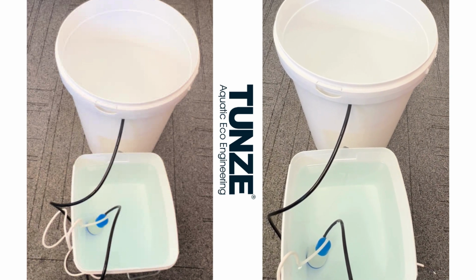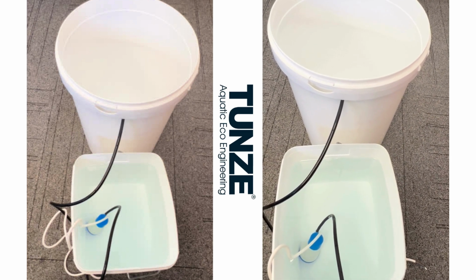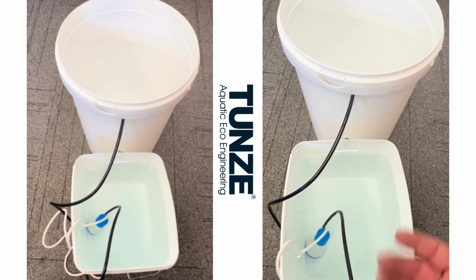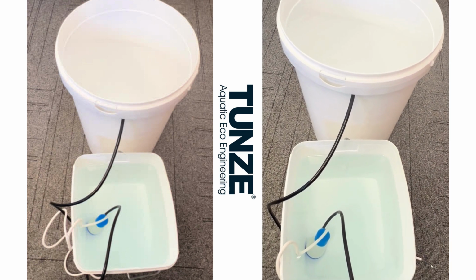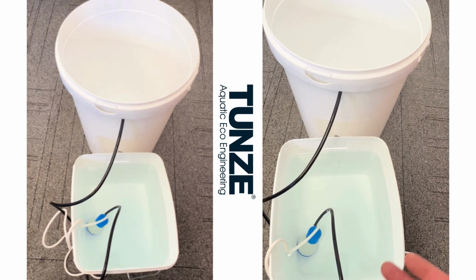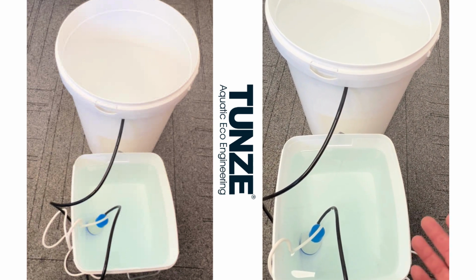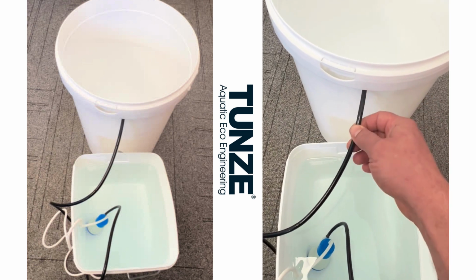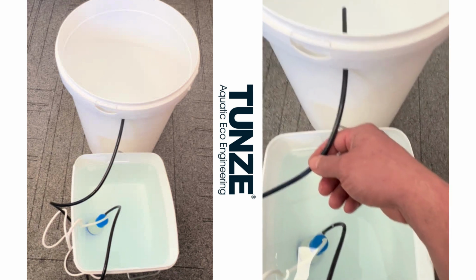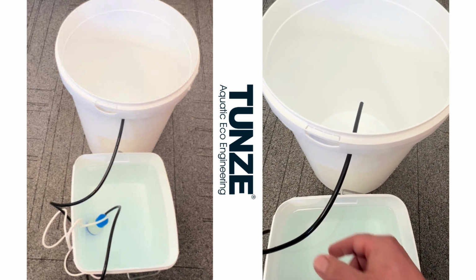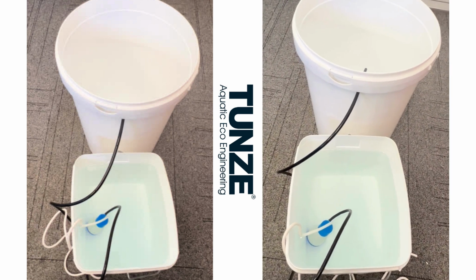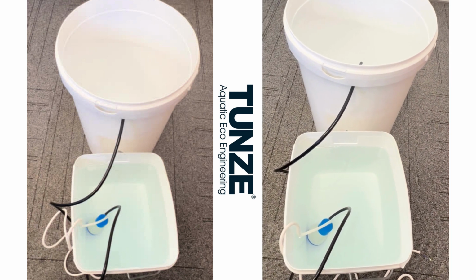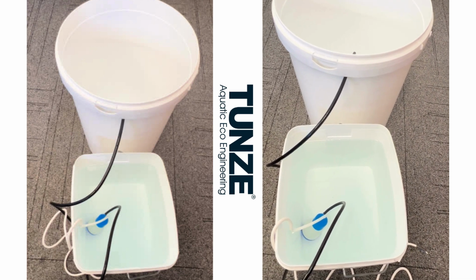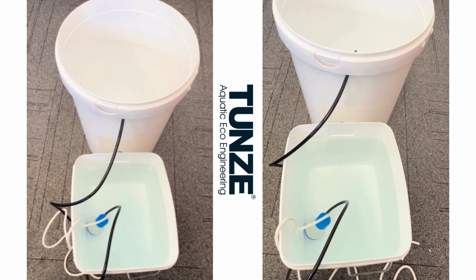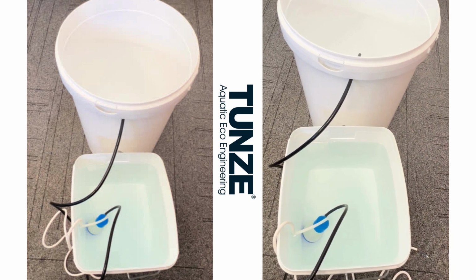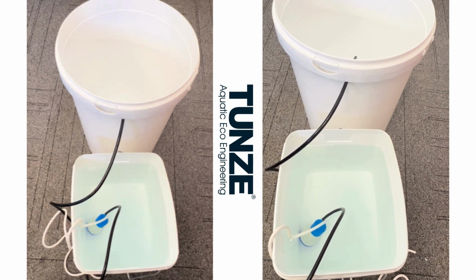There isn't a feasible way to loop the hose, and there isn't a feasible check valve you could use, because a check valve can't stop the direction of the water flow in the direction we intend it to and still work. So besides those solutions, the only real solution we have is to make sure this hose ends above the water level in the reservoir. As soon as we do that, there's no siphon, problem solved. But a check valve, we need the water to go that direction, so that's not a viable option. Besides that, a check valve is a mechanical device, any sort of air gap faucet check valve, that's another potential failure point. It's best to just get the atmospheric pressure on your side and stop it that way.